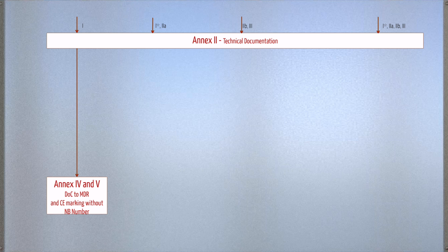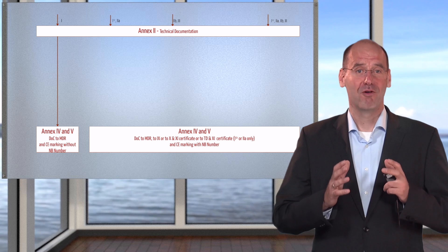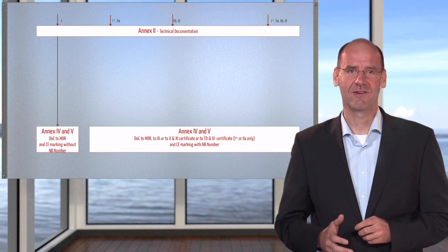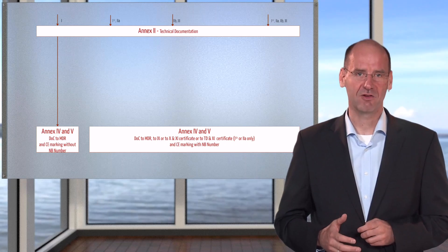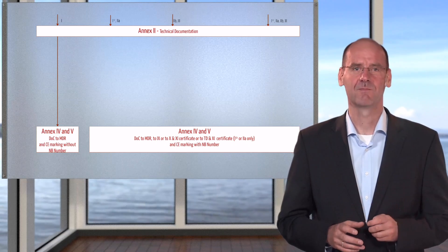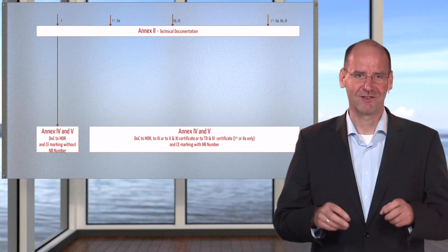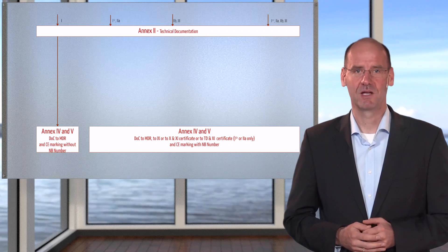Before marketing class 1 devices — these are the most uncritical ones — manufacturers just have to declare the conformity, and Annex 4, respectively Annex 5, describes how to. But this is no major deal. For all other classes, it is a major deal. Already for a class 1 device with a measuring function or that is sterile — these devices are marked here as class 1 star — a notified body must be involved.